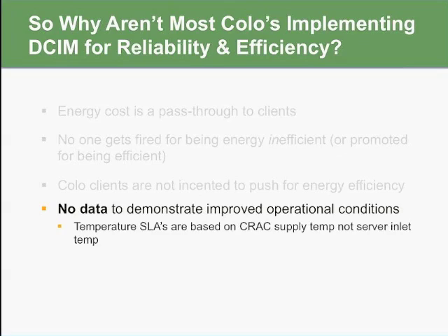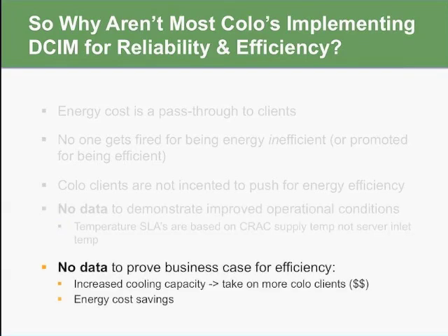This will help us improve the operational conditions within the data center and the IT equipment, and also meet our SLAs, because right now, for most SLAs, it's the CRAC supply temperature, not the server inlet temperature, that is being monitored. As a result, you could have overheating all over the data center, but as long as the supply temperature is within the SLA bounds, that's all that you need to meet. In addition to that, there's no data to build a business case for efficiency and operational benefits.